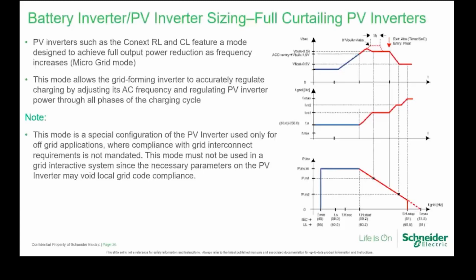It is only used for off-grid applications, where compliance with grid interconnect requirements is not mandated. It must not be used in grid-interactive systems, since the necessary parameters in the PV inverter might void local grid compliance. But as you can see over here on the right-hand side, as the battery voltage rises, the frequency will rise to derate the system, as the power requirements are not as high during absorption as they are during bulk.